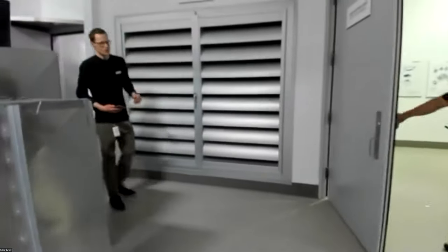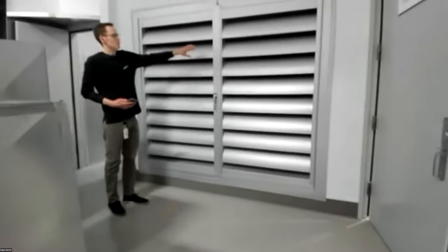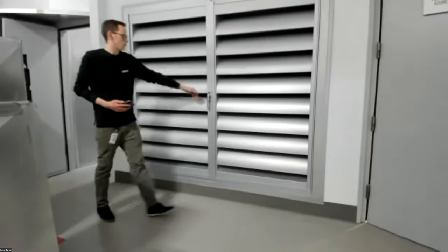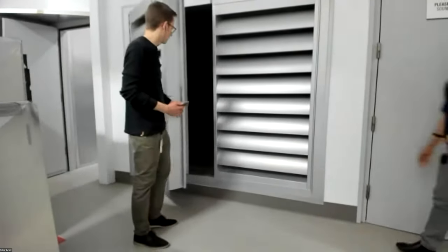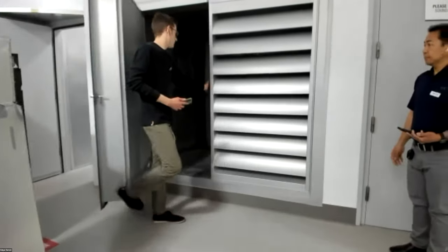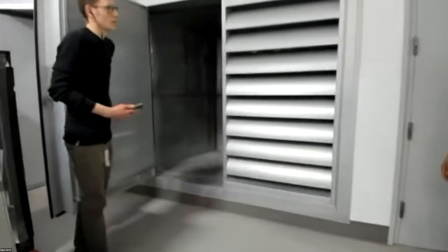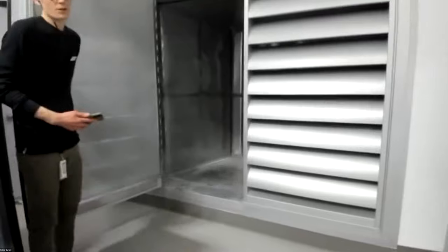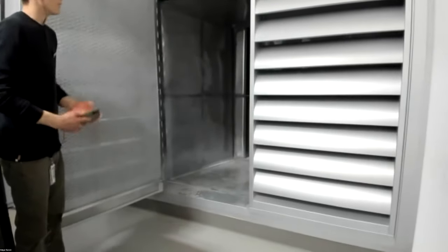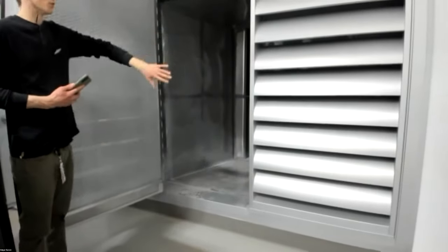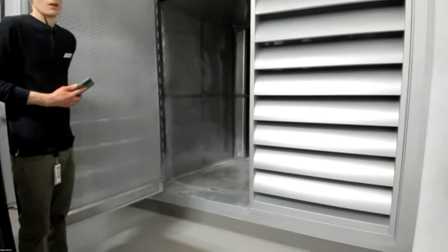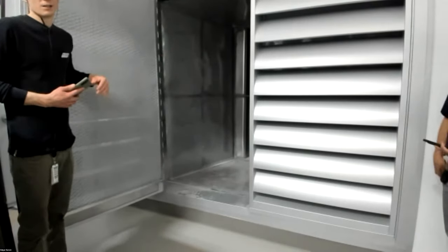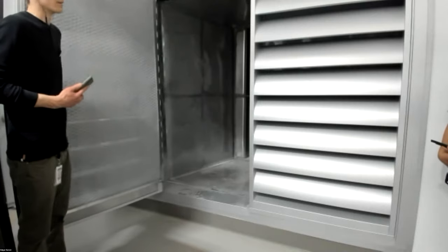So kind of at the start of the sound test, we have our acoustic louver here. So we have our airfoil louver. You take a peek inside. Essentially, this is either going to be a supply or exhaust, depending on the type of test that we're running. So we have a fan kind of on the other side of this acoustic louver and bank of silencers that we use to mitigate any sound from that fan from coming back into the test space.